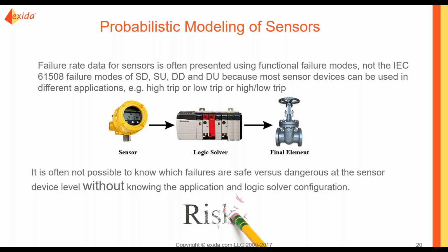It is often not possible to know which failures are safe versus dangerous at just the sensor device level without knowing the application and the logic solver configurations.